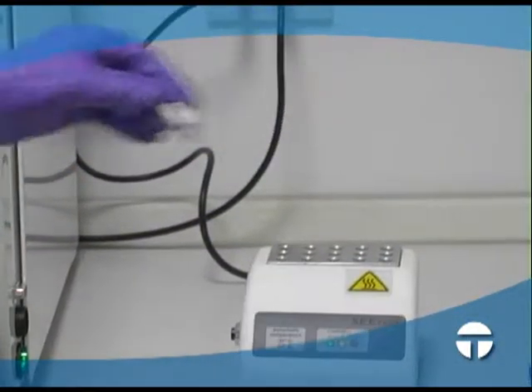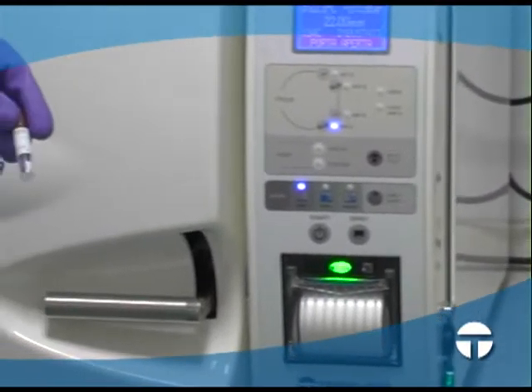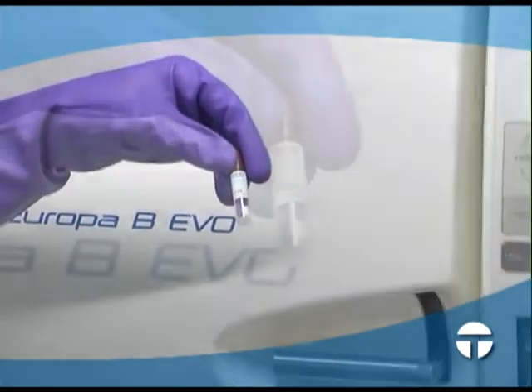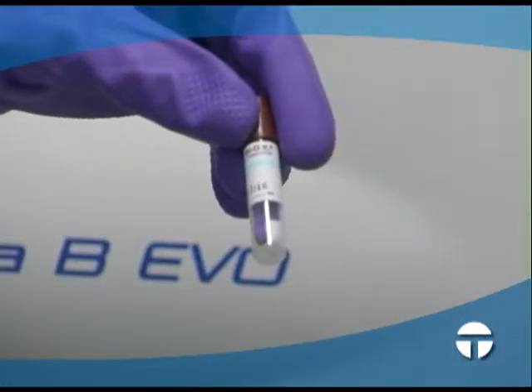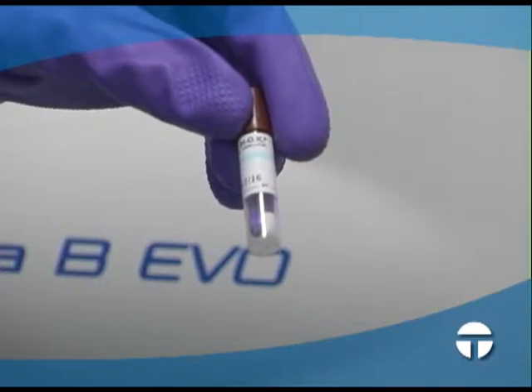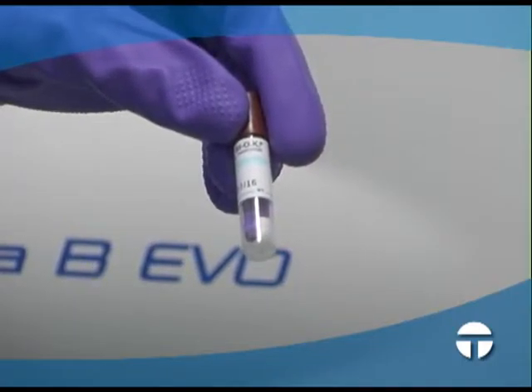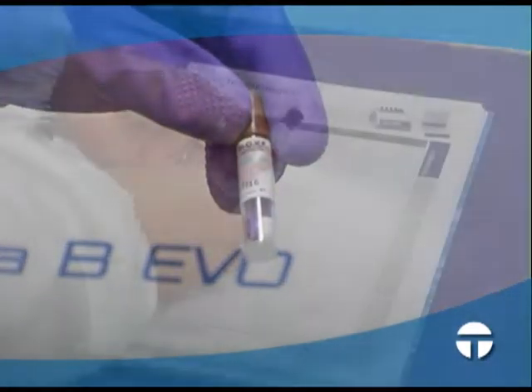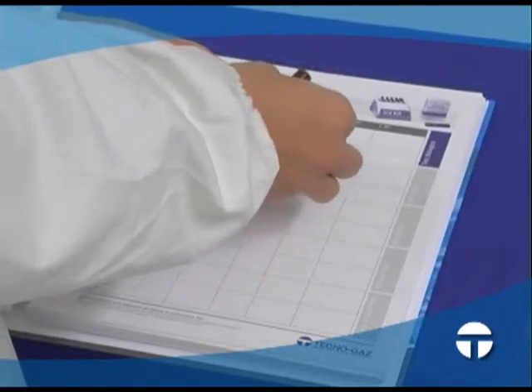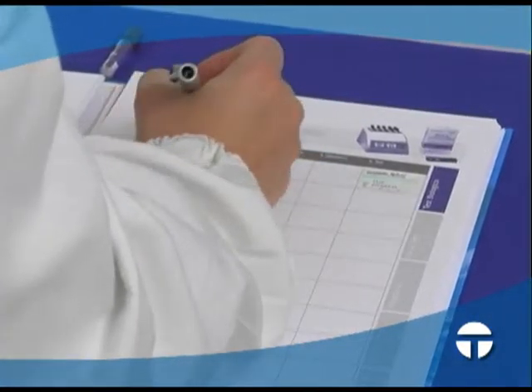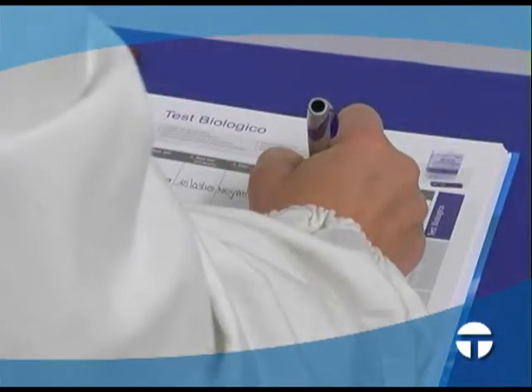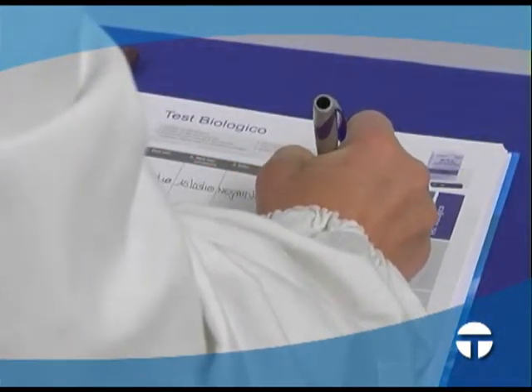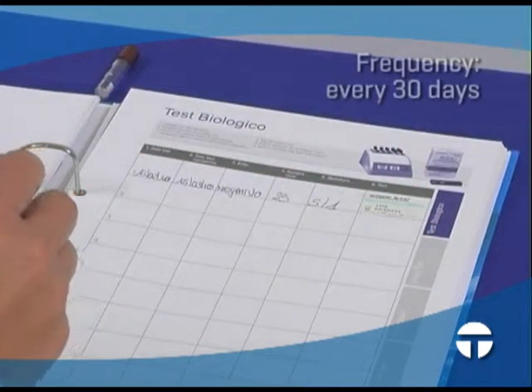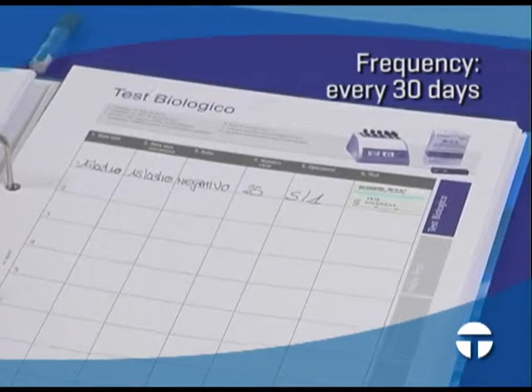If the sterilized vial has turned yellow, repeat the test. If the same result is obtained, stop using the appliance and immediately call an authorized technician. Remove the label from the vial, date, and file it. All autoclaves must pass this test. We recommend testing every 30 days.